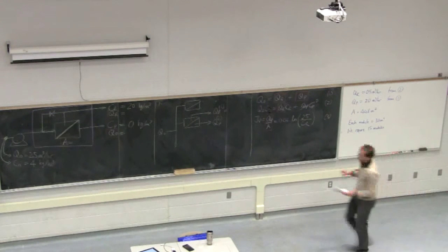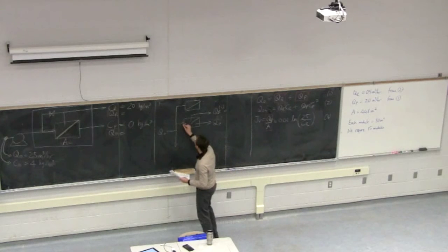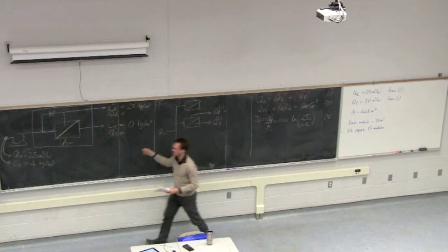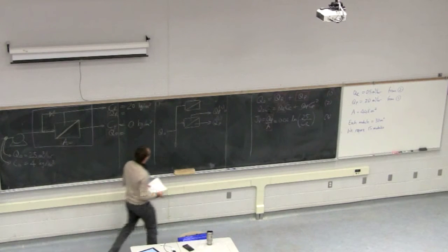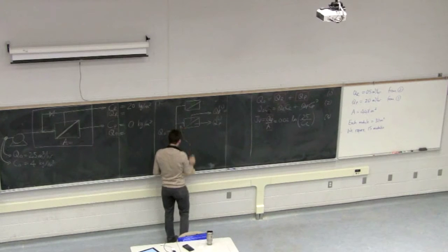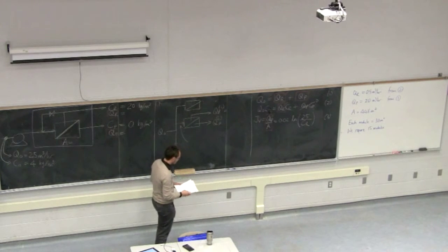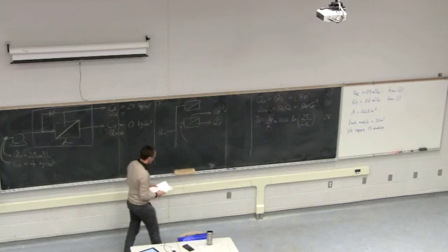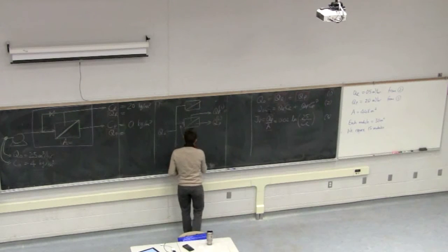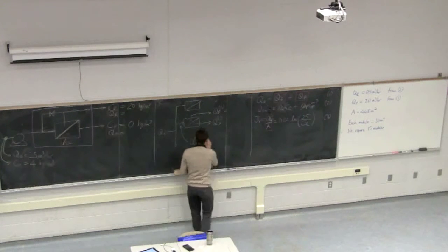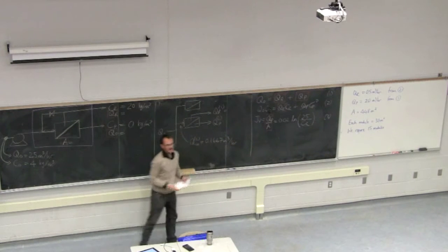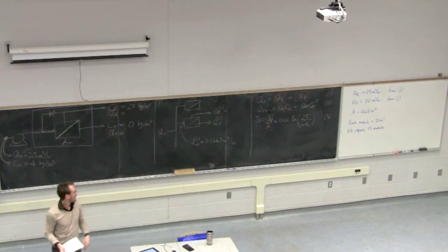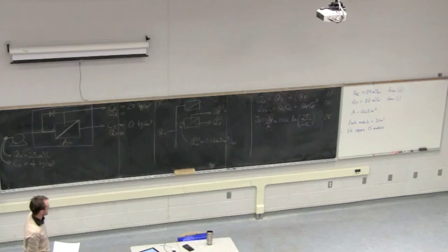Okay, so what's sent in fact to each membrane then is not the full flow rate of Q naught. We don't send 2.5 meters cubed to each membrane. We send 1/15th of that. So in fact, the flow rate going into that membrane is 1/15th, and so in this particular case, the Q naught for the ith membrane is in fact 0.1667 meters cubed per hour. So if you add up 0.1667 15 times, you get back to 2.5 meters cubed.